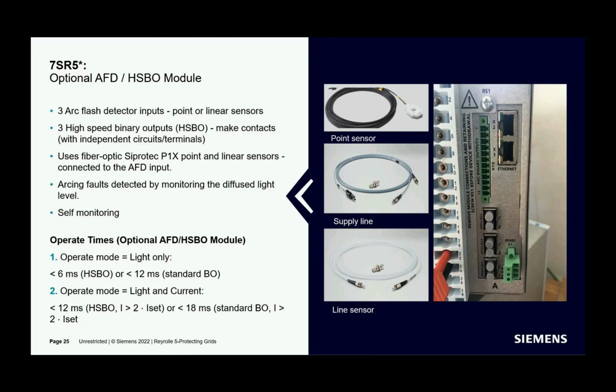The operation modes provided are light only or light and overcurrent check. So the user can configure depending on the requirement. For example, in light only mode, the whole operation from arc fault detection to output contact making can be as fast as 6 milliseconds when a high-speed output is used.